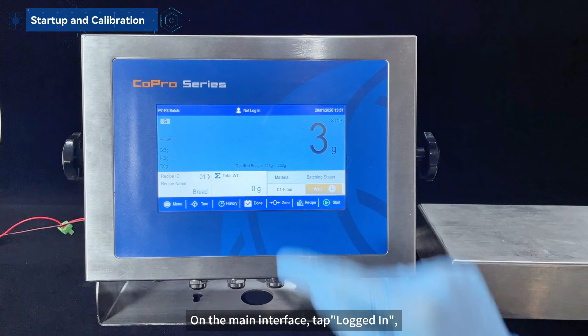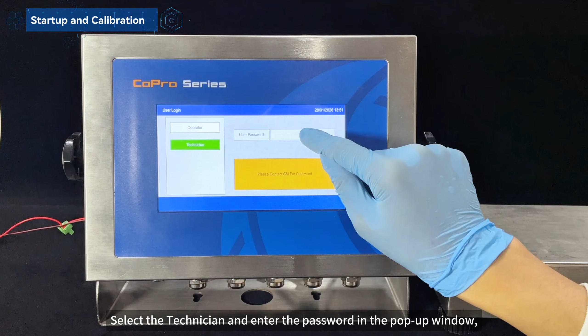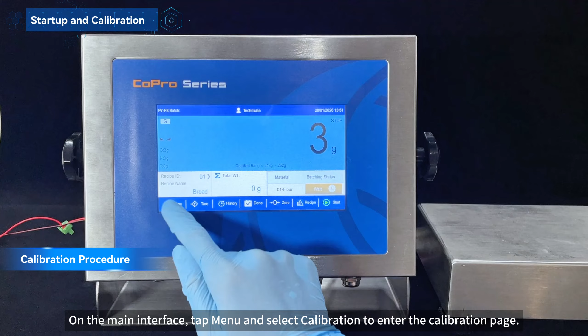When using the GMC-P7 F8 for the first time, calibration is required. Calibration requires administrator access. On the main interface, tap Logged In, select the technician and enter the password in the pop-up window to access administrator privileges. On the main interface, tap Menu and select Calibration to enter the calibration page.